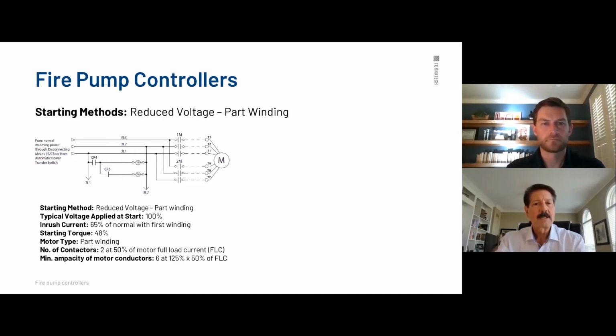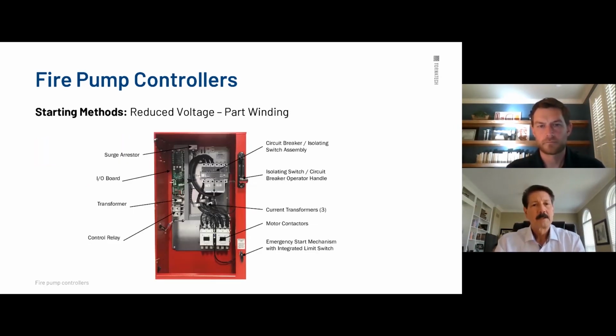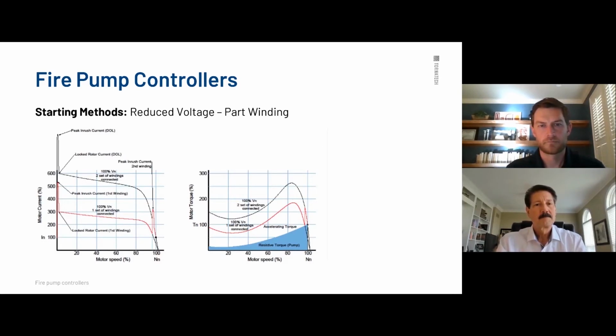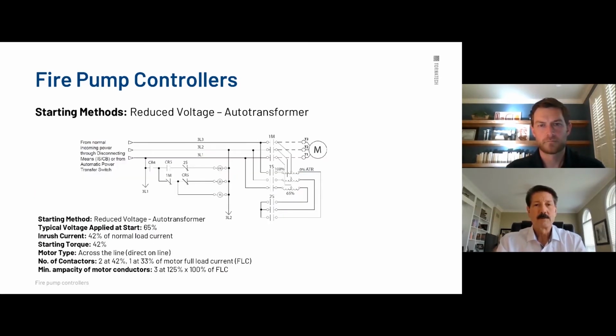That's the optimum level of the motor. Reduced voltage part winding, I'm not going to get into. Auto transformer, very brief. Again, we have a couple sets of contactors. We have taps off this transformer right here, typically 65%. There could be other adjustments, factory set, but 65 is industry standard. And again, we're starting off at a reduced voltage, which is going to reduce current.